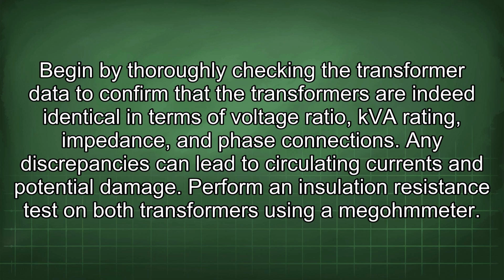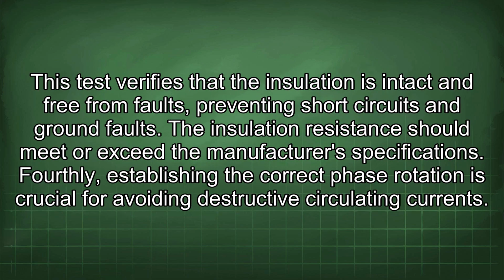Perform an insulation resistance test on both transformers using a megohmmeter. This test verifies that the insulation is intact and free from faults, preventing short circuits and ground faults. The insulation resistance should meet or exceed the manufacturer's specifications.